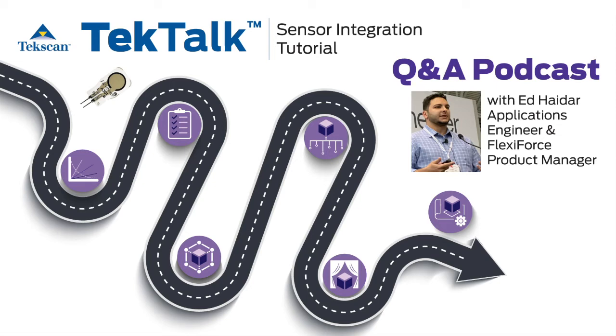By trimming the head of the sensor to make it smaller, oftentimes you're going to trim away adhesive, which could leave the two layers of the sensor apart from each other, or make the sensor prone to ingress of foreign materials. So if you're doing this as a proof of concept to try to synthesize a specific shape, what I would recommend for trimming one of our standard sensors is to take something, for example, like a packaging tape.